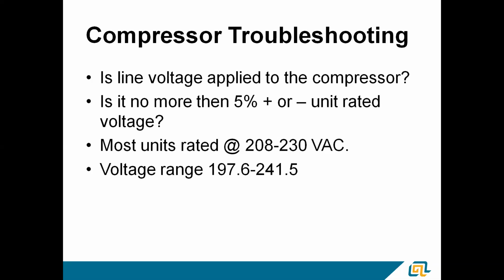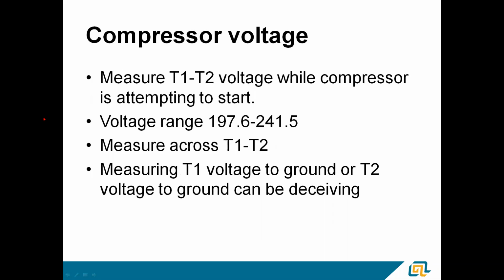So that would be a concern for me. If I saw a voltage down below 198, I would definitely be concerned. You should measure the voltage at T1 and T2 while the compressor is trying to start. A static voltage reading is nice. You're sure you got the voltage there. But what happens when you load that circuit? You flip the switch on that compressor. You want that thing to turn over and run. You've got to make sure that you're up in that 198 or better volts.